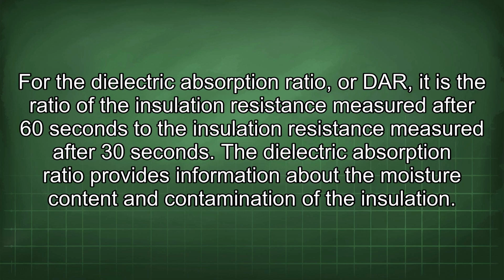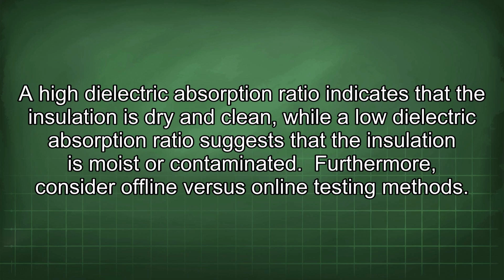For the dielectric absorption ratio, or DAR, it is the ratio of the insulation resistance measured after 60 seconds to the insulation resistance measured after 30 seconds. The dielectric absorption ratio provides information about the moisture content and contamination of the insulation. A high dielectric absorption ratio indicates that the insulation is dry and clean, while a low dielectric absorption ratio suggests that the insulation is moist or contaminated.